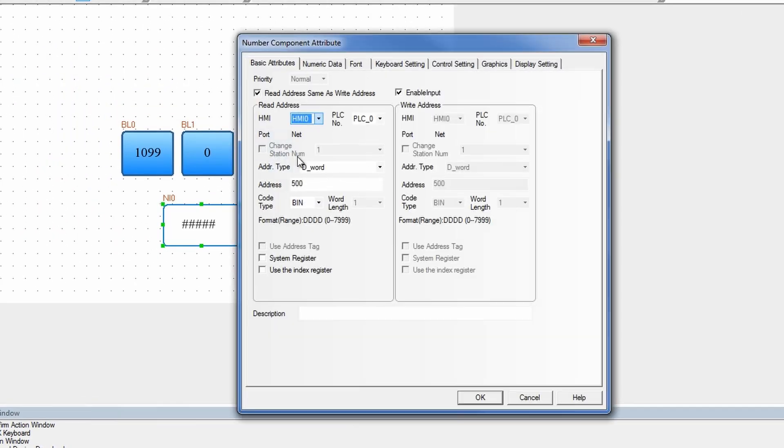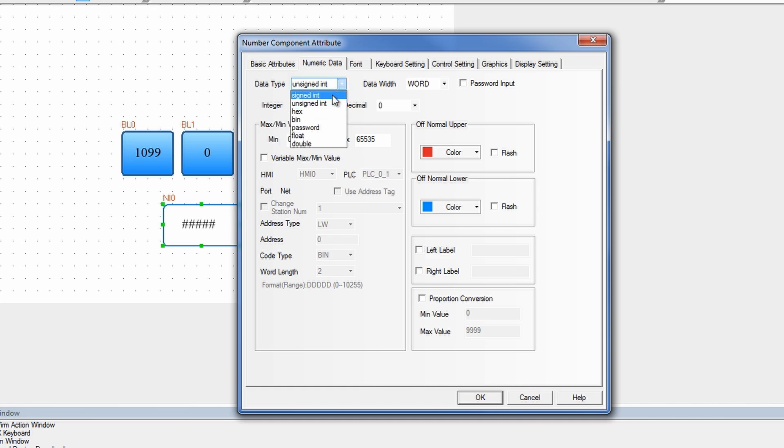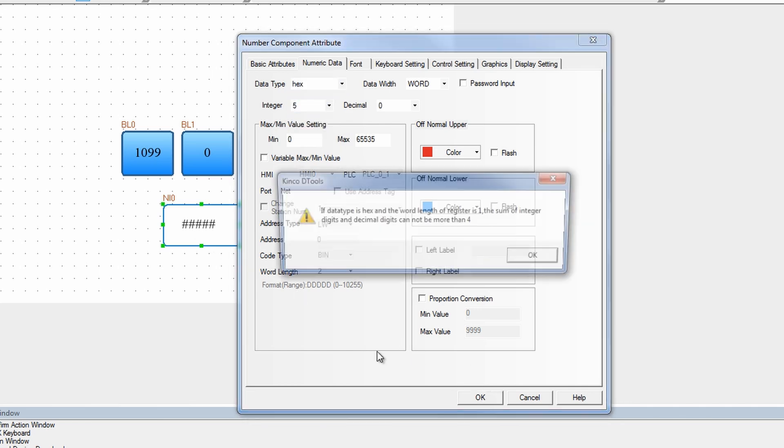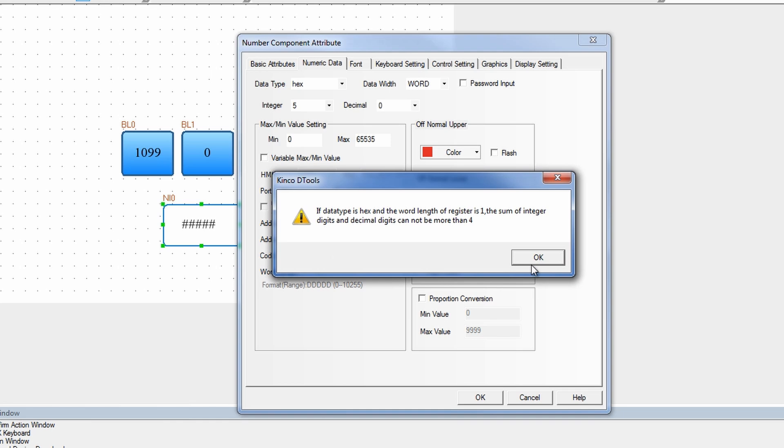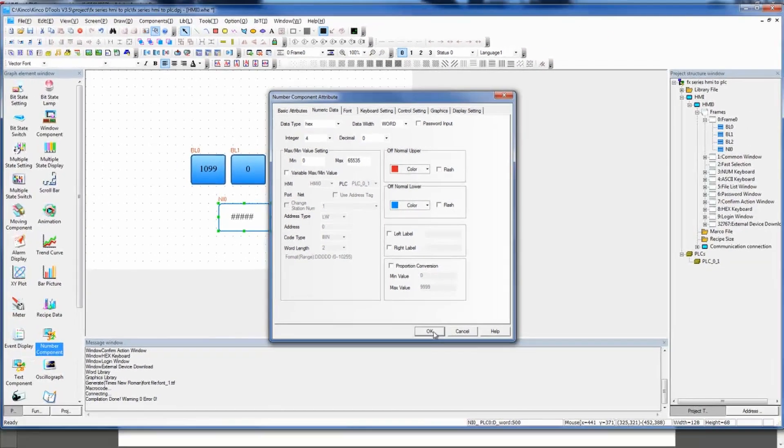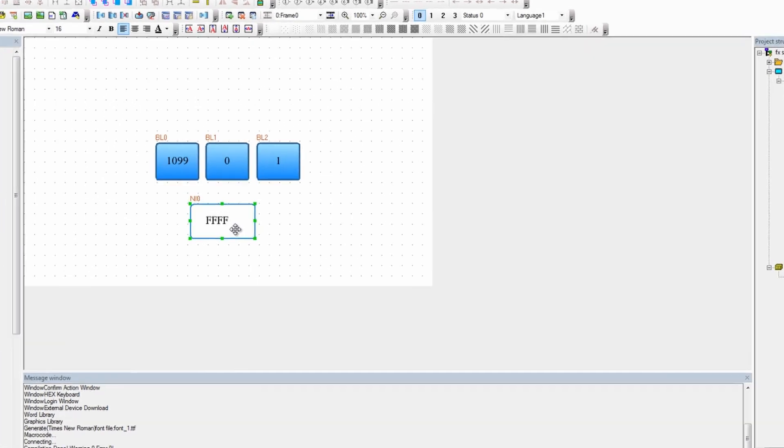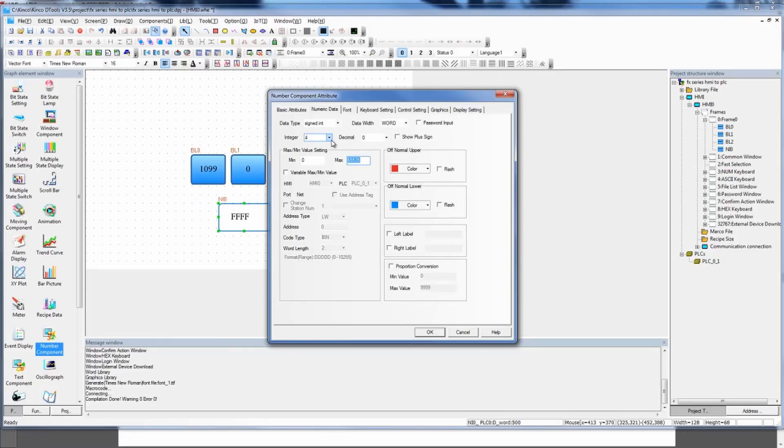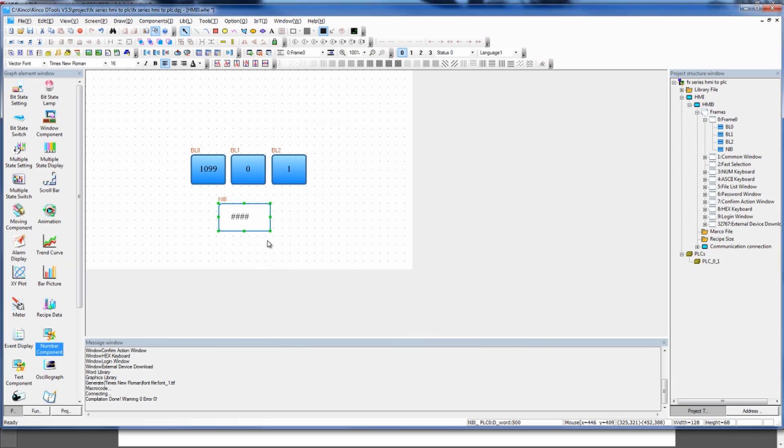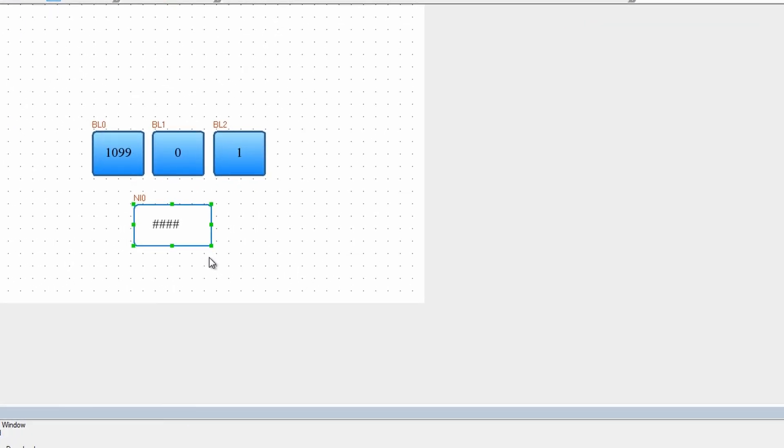Now let's say your data in there isn't necessarily an unsigned integer. Say you have a signed integer in there. Say that you have a hex value in there. If you put in a hex value, then this isn't going to show numbers. I'm going to use four because we can't use more than four. It's going to show our hex values. If I'm looking in there and say I want to make sure that I have 0601 in there, I can show that off as my hex values. If I wanted to show that it was going to be some other value, like a signed integer, I'm going to have to reduce this value to 9,999 because that's the maximum you can have with signed integers. That last bit is going to be positive or negative, but this would show here.